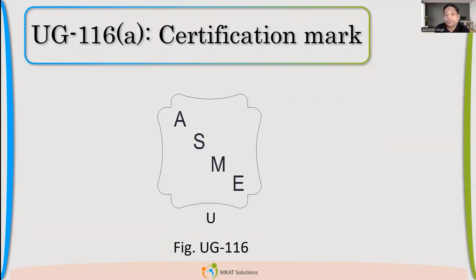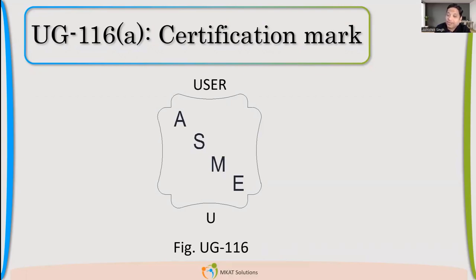The code gives an exemption in one case: the manufacturer can use his own inspector. But in that case, the stamping will not look like the standard U stamp — it will say 'User.' That word gets added. ASME allows this only when you are the end user — meaning the manufacturer himself will use the vessel. He is the end user, so only then can he manufacture under ASME, use his own inspector, and apply this mark. But 'User' must be written, and the end user has to be the same manufacturer.